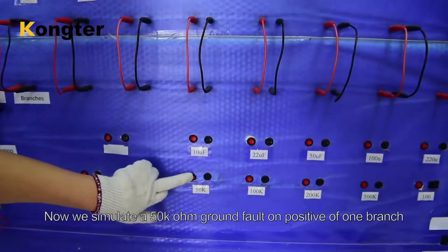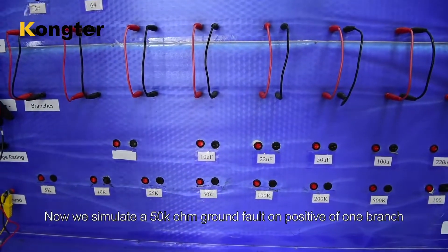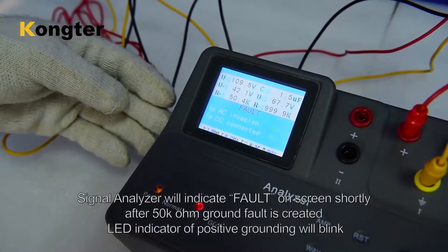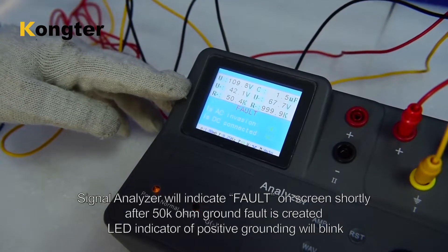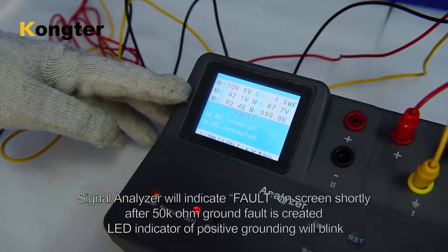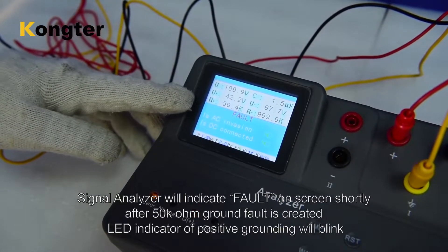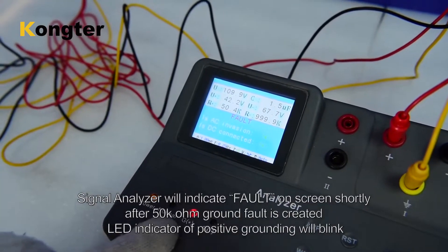Now we simulate a 50k ohm ground fault on positive of one branch. Signal analyzer will indicate fault on screen shortly after the ground fault is created. LED indicator of positive grounding will blink.